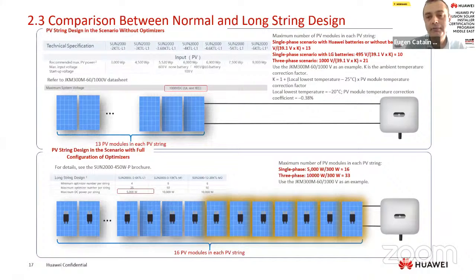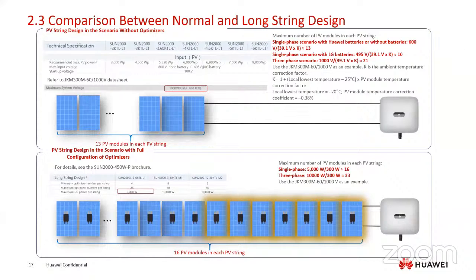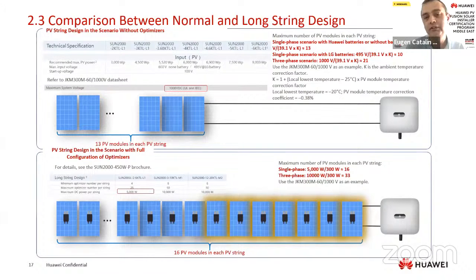I need to add here an example of a customer of ours. The example was like this. He bought a 20 kTL M2 inverter. He installed the inverter in long string design. So he put the maximum power per string, 10,000 watts per string. This inverter model M2 has 4 strings, and he put 40 kilowatts. So he doubled it in long string design. And he waited for the inverter to produce 40 kilowatts. But it's not possible, yes?